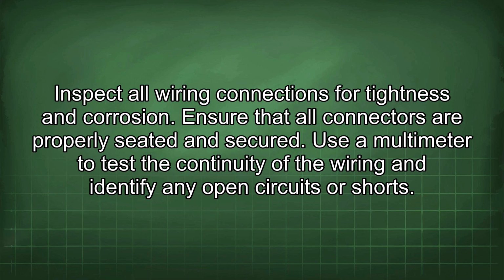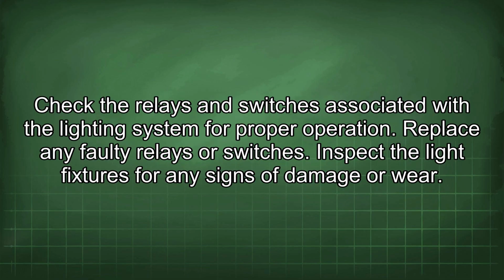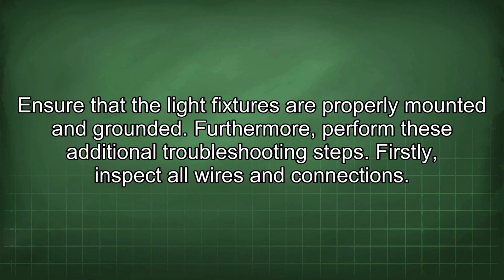Use a multimeter to test the continuity of the wiring and identify any open circuits or shorts. Check the relays and switches associated with the lighting system for proper operation. Replace any faulty relays or switches. Inspect the light fixtures for any signs of damage or wear. Ensure that the light fixtures are properly mounted and grounded.